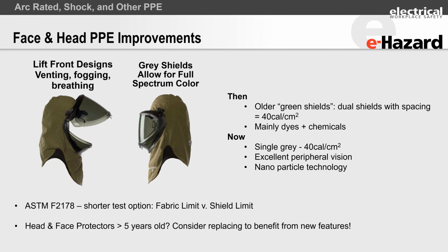These new technologies are fantastic, they've now got a shield up to 20 cals that looks perfectly clear. It's 100% light transmission, but it does block certain wavelengths, including infrared and UV, and a certain amount of light that's not enough for you to visually notice the difference. Up to 100 calories, they're a lot clearer now, and they don't have to be the old green shields.